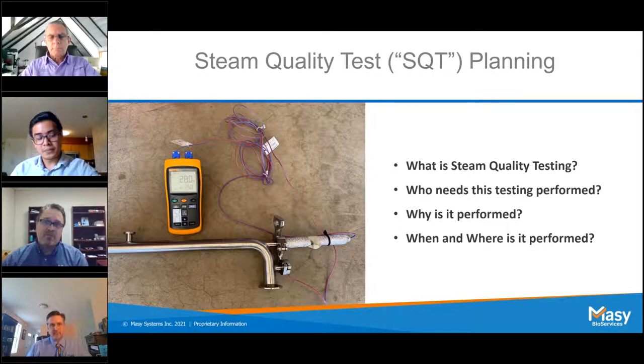And then the third parameter is dryness. We're measuring the steam to make sure that there isn't an excessive amount of liquid water in the steam. We want that steam to be gas phase. That will be measured to within a certain parameter so that we know we're getting gas phase steam versus a lot of liquid or condensate into the sterilization environment. Back to you, Rob.